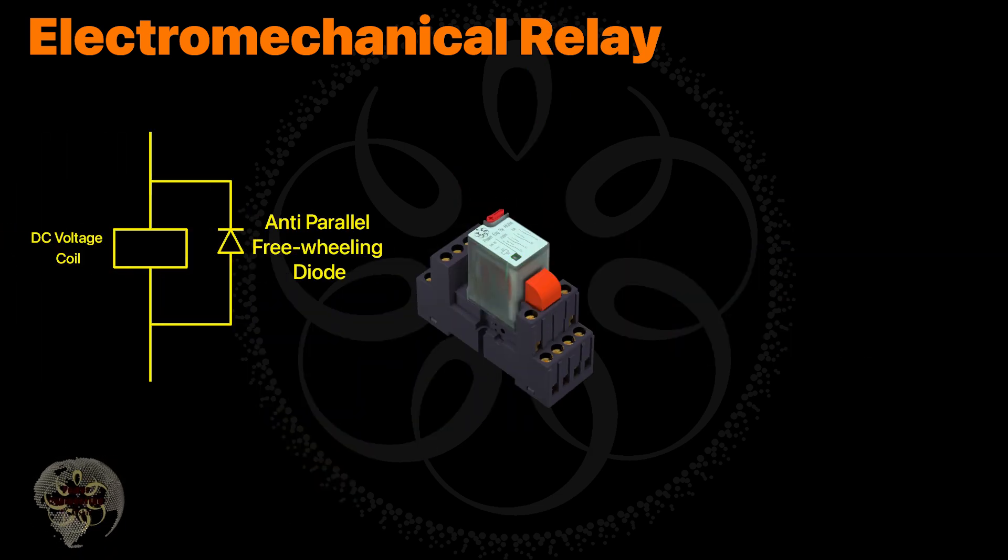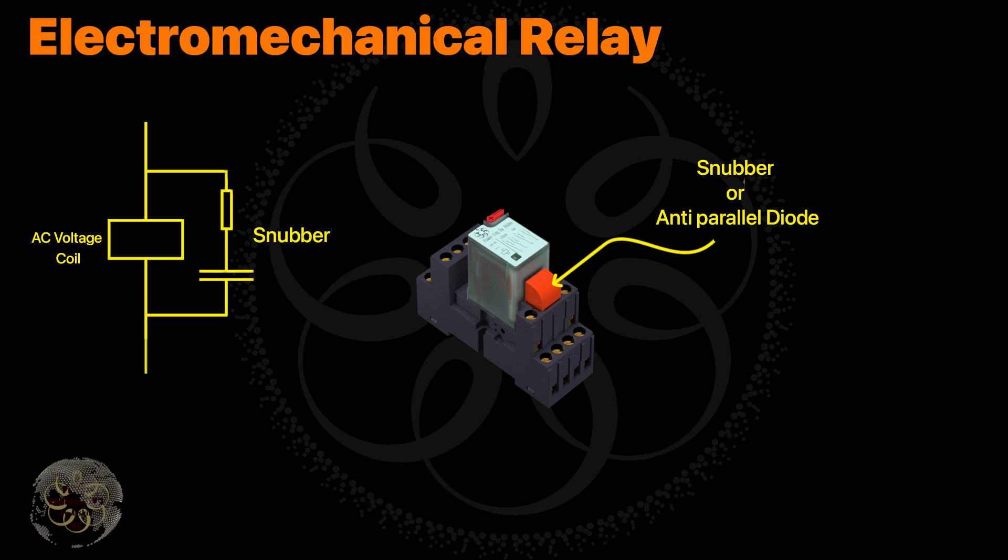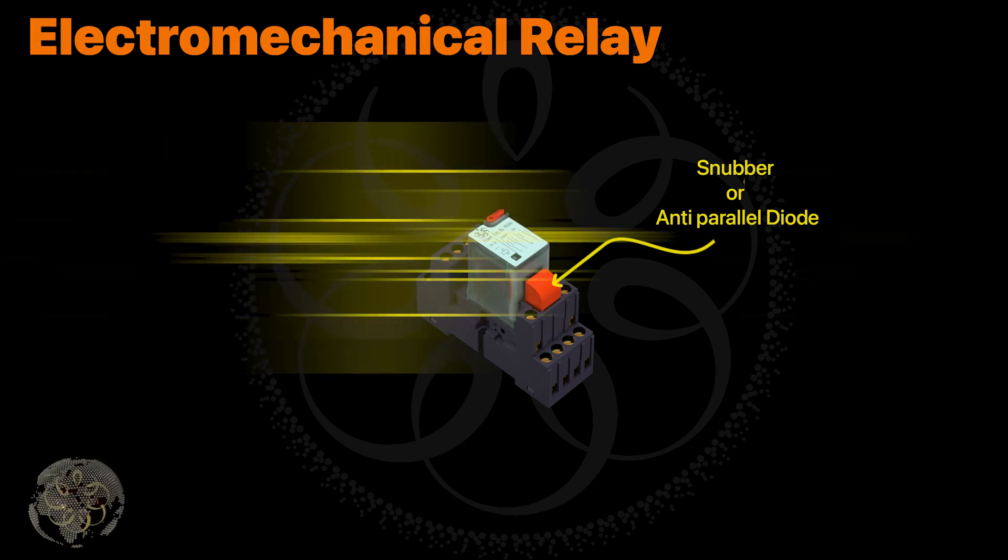This diode prevents voltage spikes, dV/dt, caused by the sudden interruption of coil current. However, this diode cannot be used in AC relays. Instead, AC relays use a snubber circuit, which consists of a resistor and capacitor connected in series.